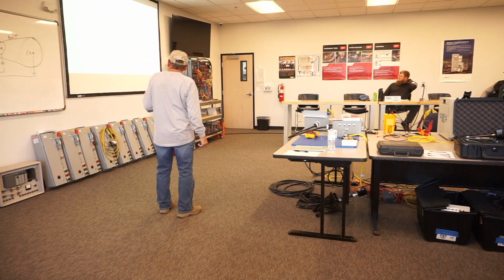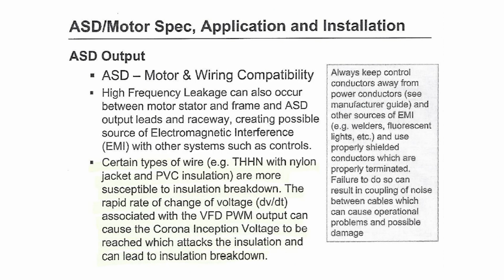And there we go. THHN wire. Insulation breakdown. And that rapid change of voltage, dVdt. Delta voltage, delta time. The amount of voltage change and the amount of time that it's occurring in. That's what dVdt stands for. Delta voltage, delta time. And it will break insulation down, causing heat, melting insulation.